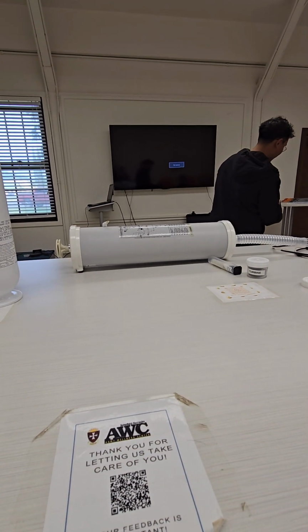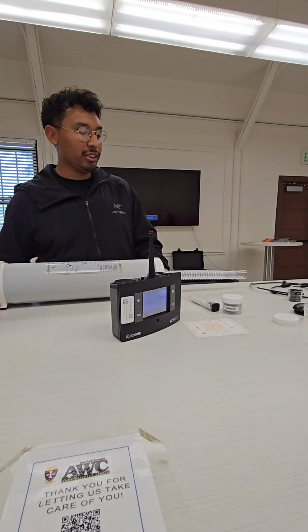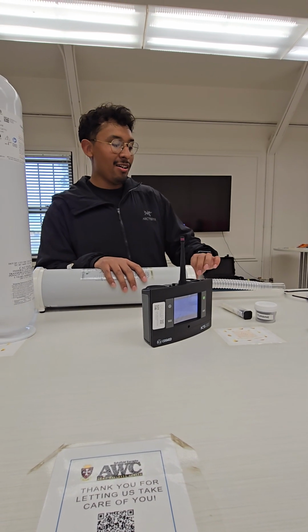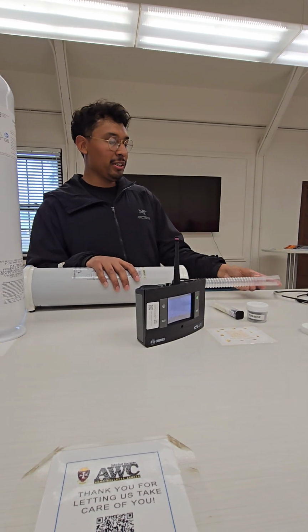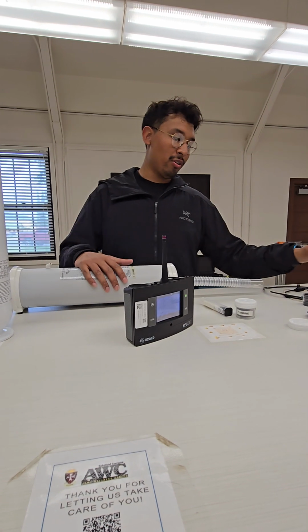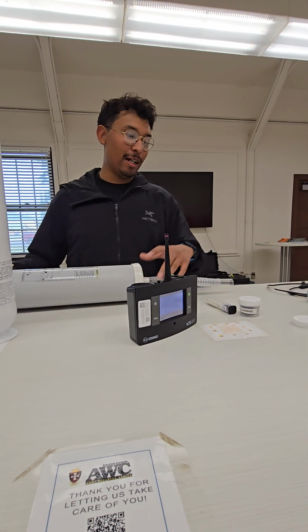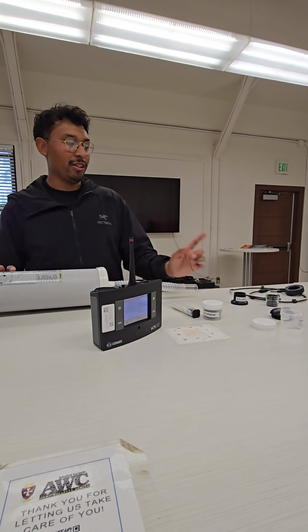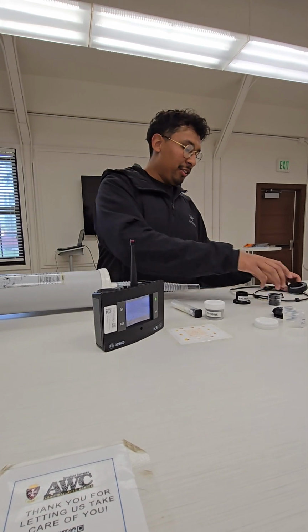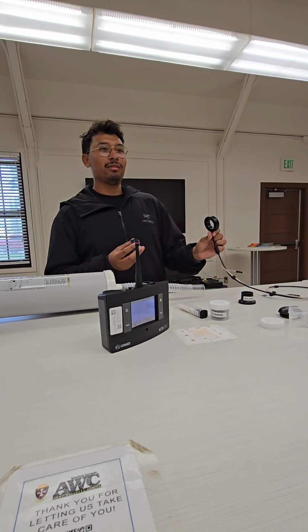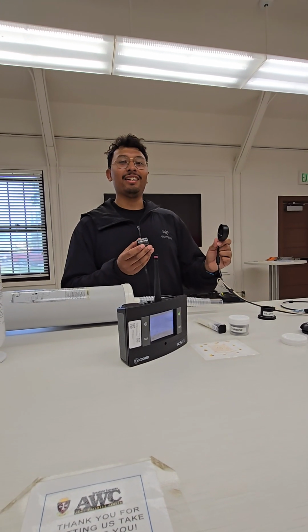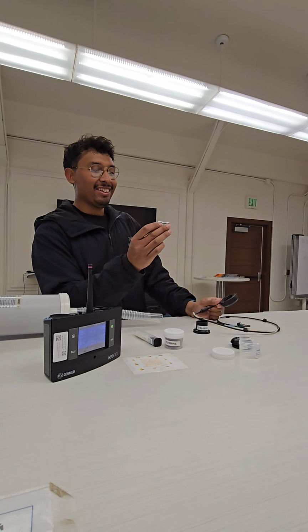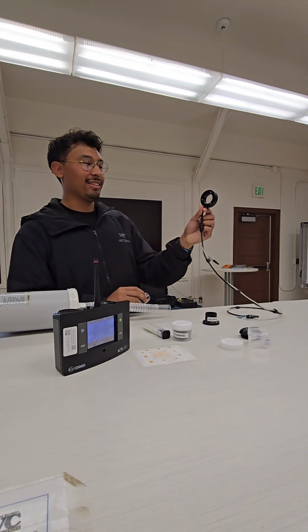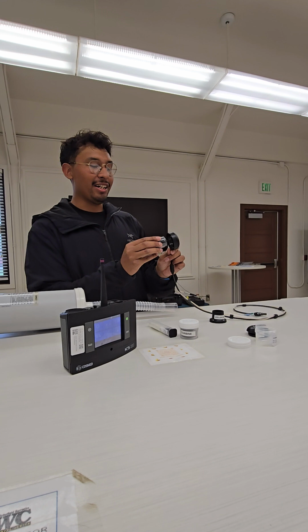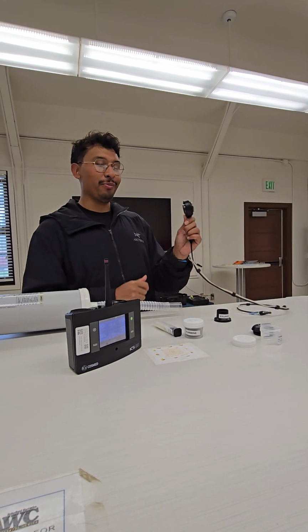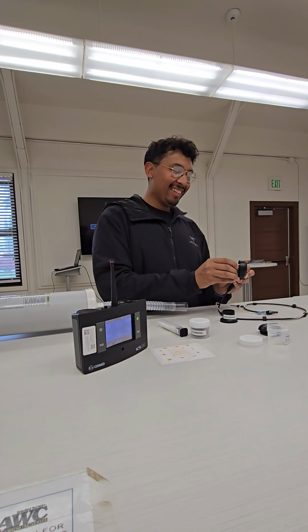So this is your 3-liter syringe. I'm sure you've used them a lot of times. You have the corrugated tubing, and then the adapter for basically the other adapter, which is this guy, and then it'll go into the flow meter. Do you guys know how a flow meter works? Do you care to know? Go ahead and review it. This is a turbine on its own, and then this is an optoelectronic reader on its own. Together, we get a flow meter. So that's what this guy is.